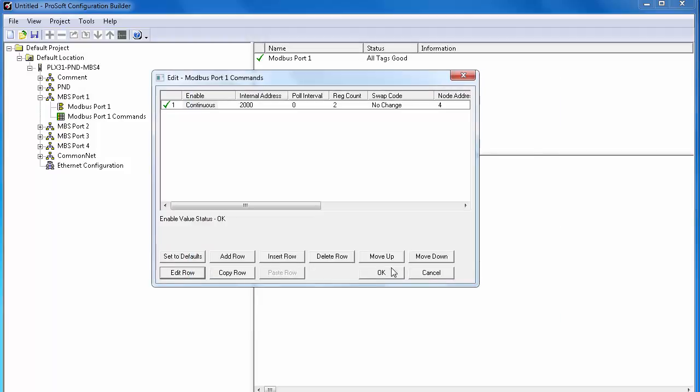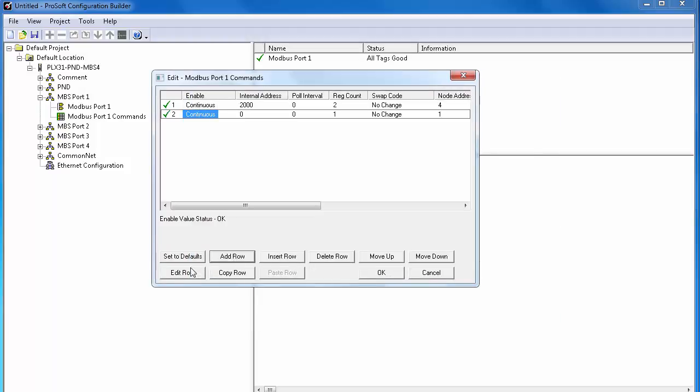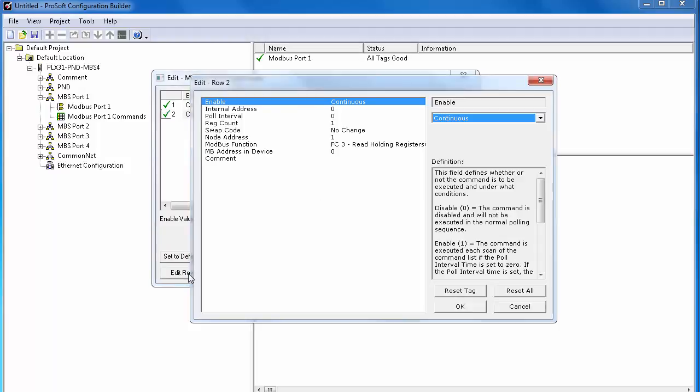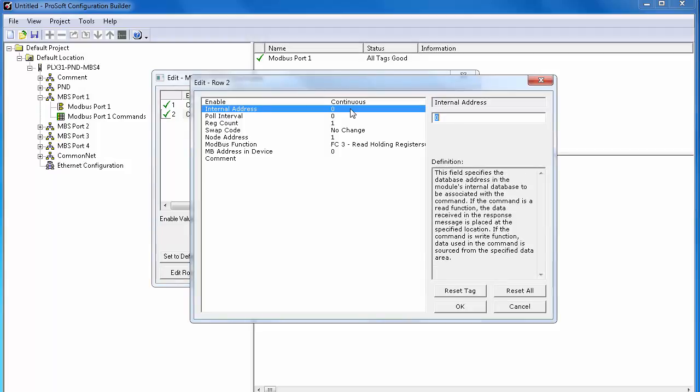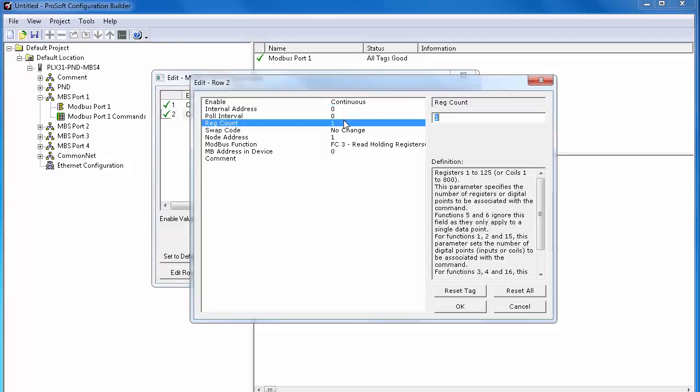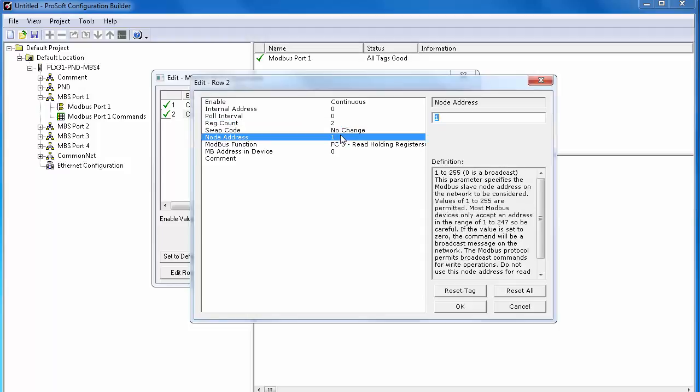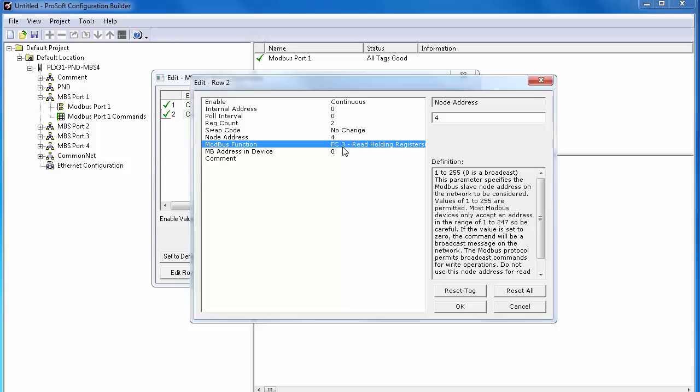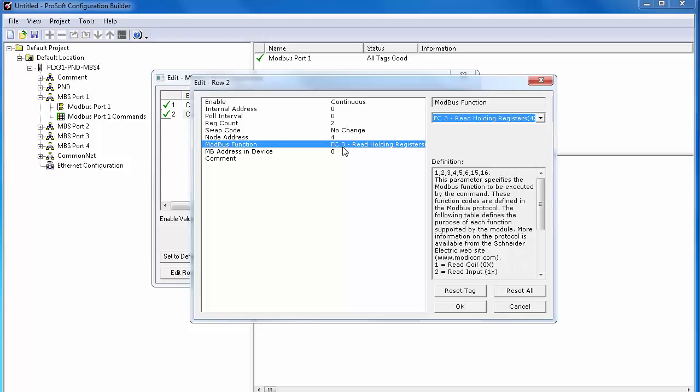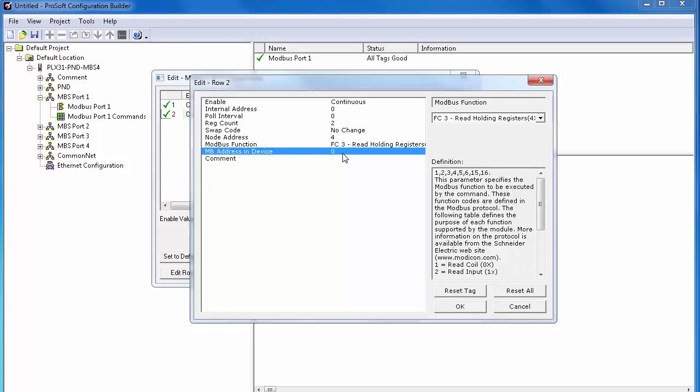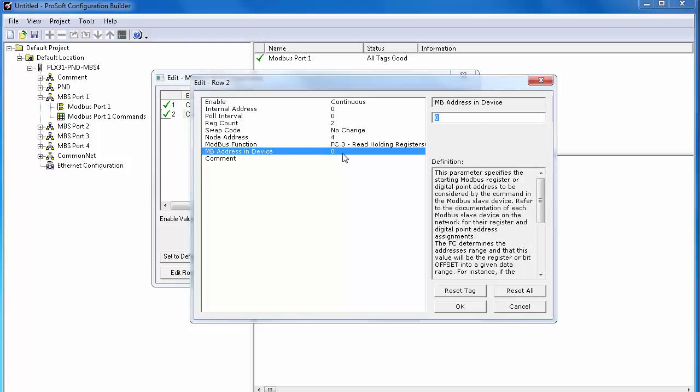We'll create a read command. So we'll add another row and edit that row. Set the command to run continuously as well. Internal database will be zero. Two words for register count. Node address will be 4 again. Function code will be 3 to read multiple words. Address in device will be 224. And click OK.